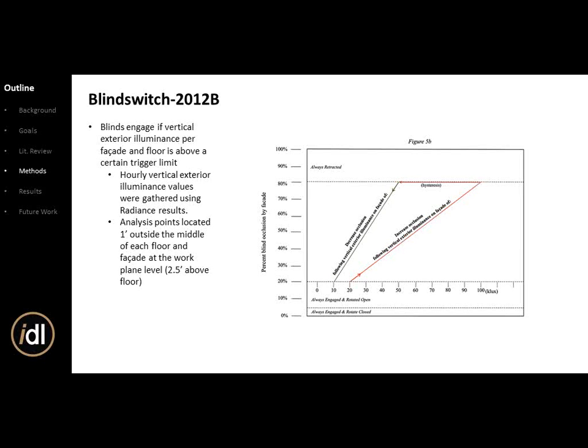For Blind Switch B, percent occlusion increases as vertical exterior illumination rises above trigger values in kilolux. The 30 to 40% blinds will trigger at about 17,500 lux. There's also a hysteresis effect — once blinds are triggered to full engagement at 70%, they will only retract if illumination drops to a lower set point. So the 50 to 60% window engages at 72,500 lux and retracts only below about 36,000 lux.